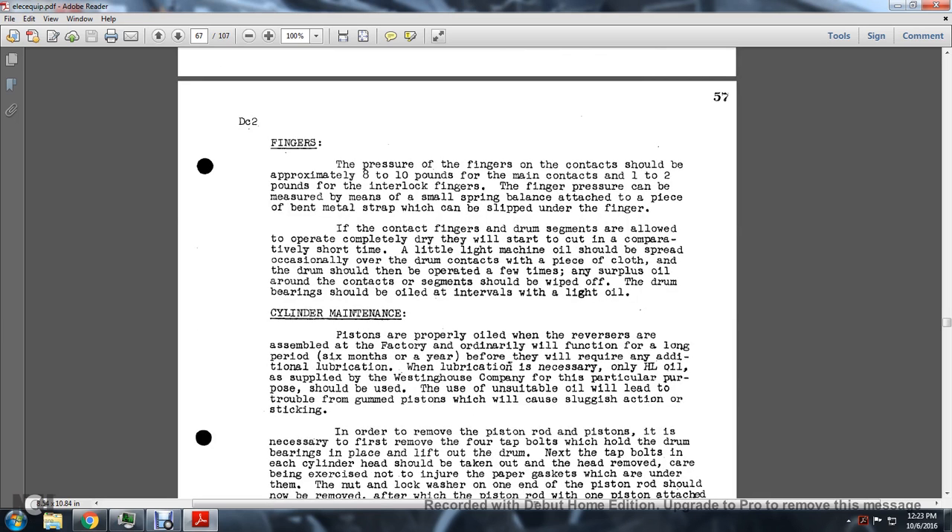The pressure of the fingers over the contacts should be approximately eight to ten pounds for the main contacts, and one to two pounds for the interlocking fingers. The pressure can be measured by means of a small spring balance attached to a piece of bent metal strap slipped under the finger at the point of contact.